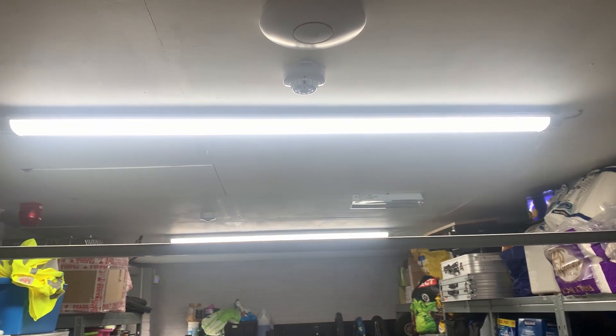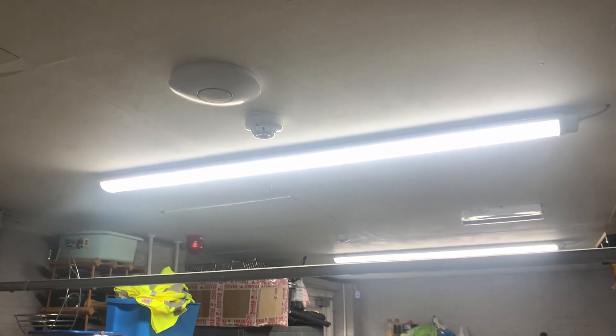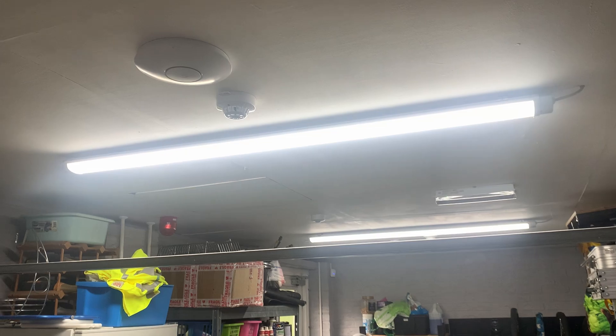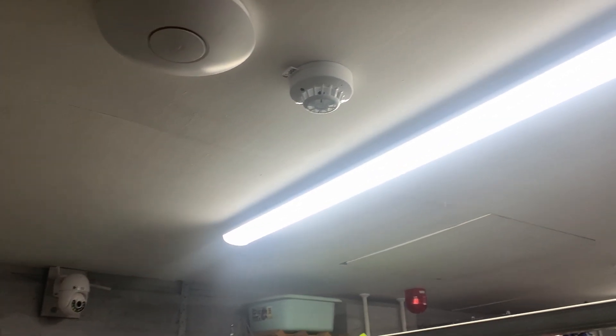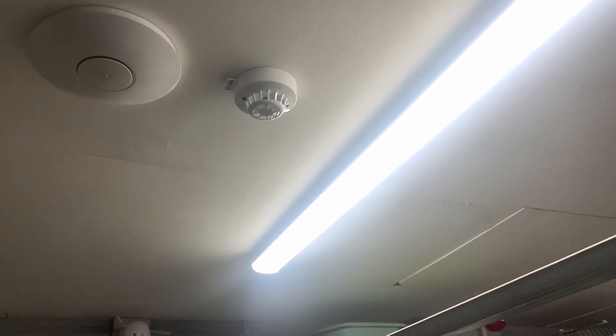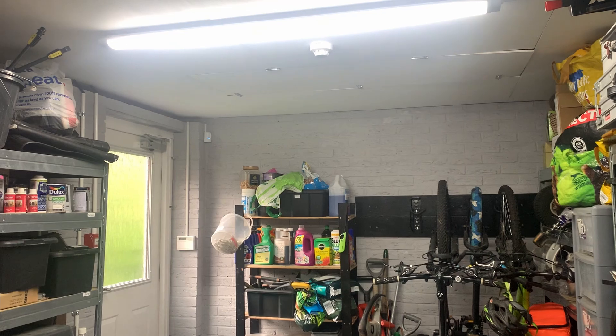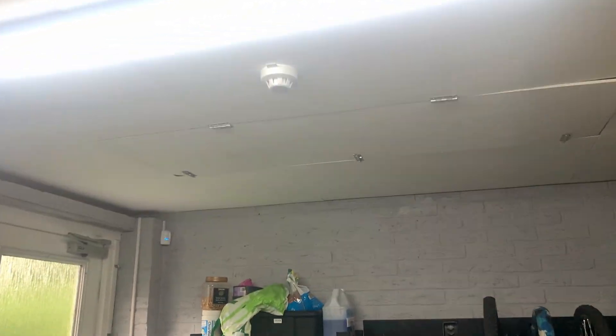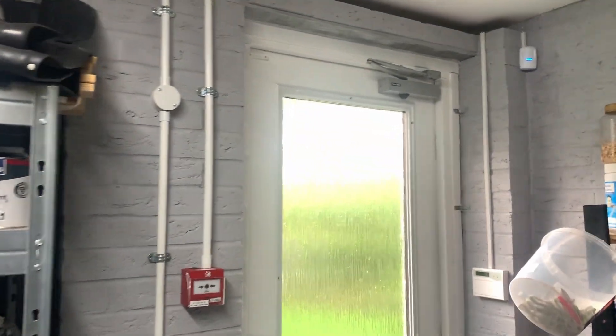In the garage, we've got a heat detector in the more workshop area. I haven't actually had a false alarm in this area, but just in case I do, I decided to swap out the Discovery smoke for a Discovery heat — I think it's more appropriate. The smoke detector on the other end is still a Discovery optical, and same with the garage loft just up there.